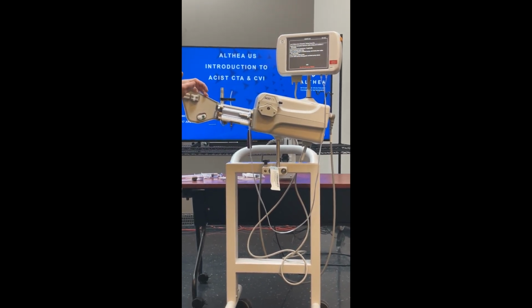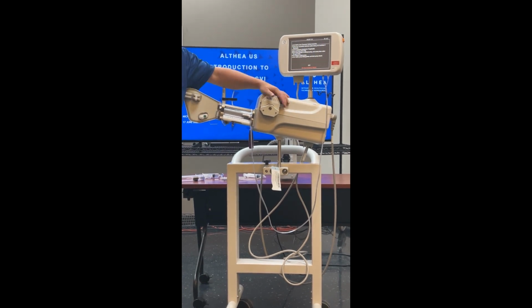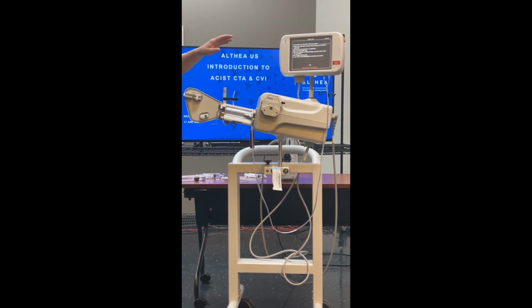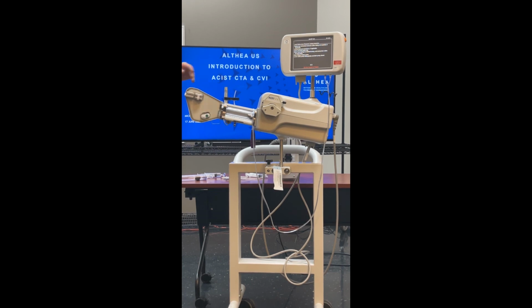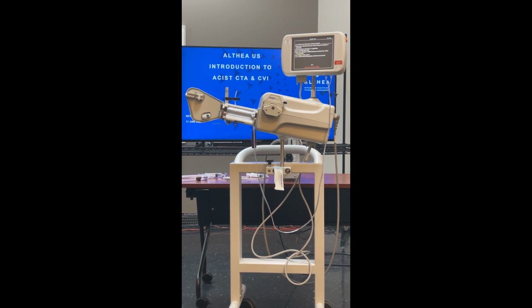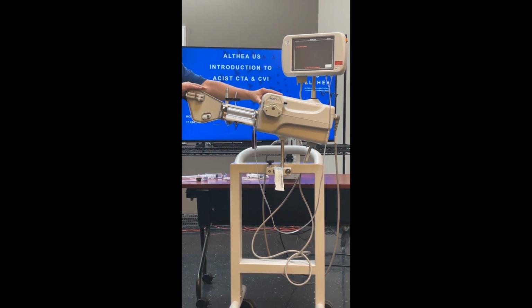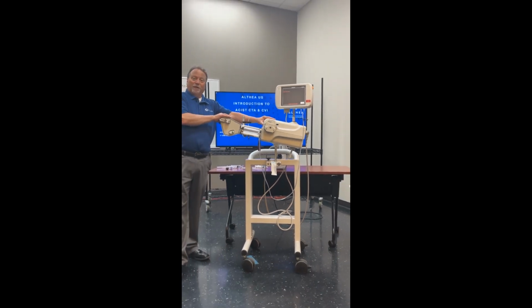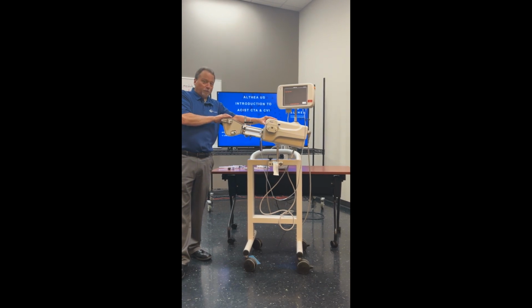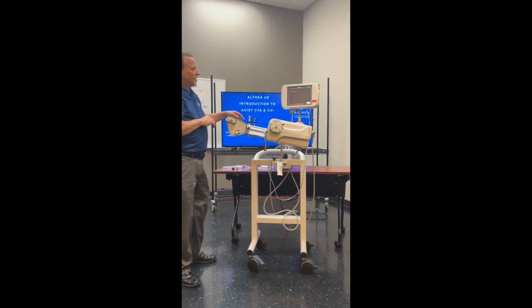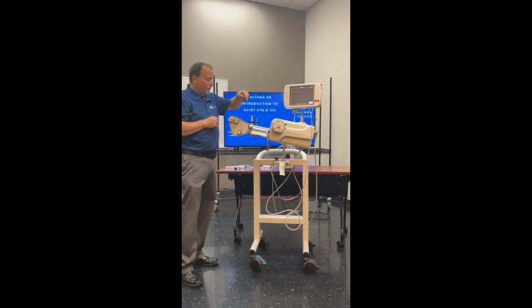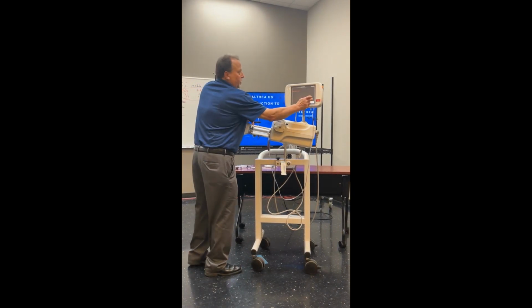Now it tells me that I can advance on to loading saline through the peristaltic pump, but we're not going to do that because we're not concerned with that. So now it's loading the syringe. Even though there's nothing in there, we simulated the syringe. And if you do PMs on these, you actually have to go through 60 to 70% of the PM just to get to the point to start the PM, which I find is very interesting. Now it says syringe valve closed, so I'm going to use my finger again, insert it into the sensor, and hit OK.